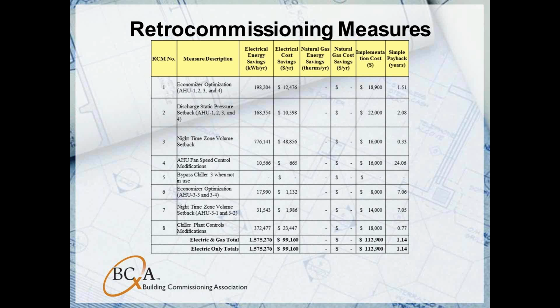And as part of that, RCM 5 here, we want to bypass chiller 3, which is one of the series counterflow chillers, and only operate chiller 5. So we would operate a 400-ton chiller as our first stage of mechanical cooling and have much better part load control.